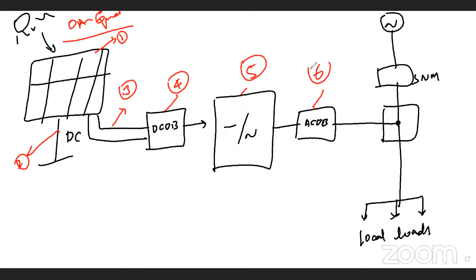Now, to route the cables, there are some more components involved, which include PVC pipe, clamps, screws and so on. The next part is DC earthing and AC earthing. Then there is one more thing, the LA, lightning arrestor. So this is E1, this is E2, this is E3. At any point, the DC earthing and AC earthing should not be mixed together because the fault current of DC and AC is different. So E1 has to be separately grounded, E2 has to be separately grounded, and the lightning arrestor has to be separately grounded.